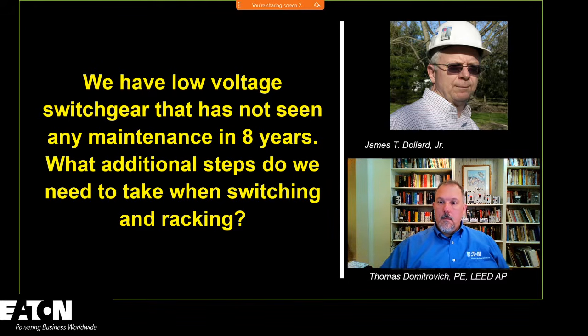Well, NFPA 70B, the guide for electrical maintenance, is going to tell us every 3 years those low-voltage power circuit breakers need to be maintained. And the manufacturer may say, well, it's 5. So let's take a look at it. Somewhere between 3 and 5 years, they need to be maintained. There are moving parts. There's grease, there are lubricants, and if they're not moved, if they're not lubricated properly, that can turn into cement, and you can increase your opening time, or it may not open, or one pole may not open.